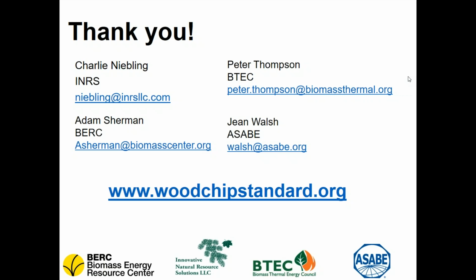So it looks like the next question was from Andrew Perchlik, asking, can there be greater than 50% moisture content and less than 1.5% ash? If so, what is the chip classification? So if it's greater than 50% moisture content, it is a grade B, whether or not it has a lower ash content. Great question, good clarification. Probably not entirely clear from the flow chart at first glance, but it's an either or type thing where even if you're lower on one, if you're over 50% moisture content, you are in the grade B category. Hopefully that answers your question.